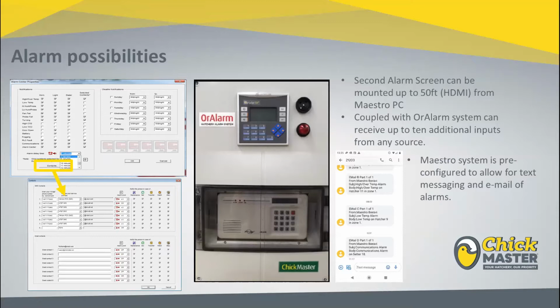The system also has the ability to disable notification by selecting the day of the week you would like to disable it, and from what time to what time. And again, remember, you'll be selecting the times that you do not want it to send out notifications or dial out messages. There's also an alarm delay built into this system, and the idea with the alarm delay is, one, give it some delay so you don't get every little nuisance alarm that triggers, but also don't give it a huge delay, maybe somewhere between 1 to 3 minutes, I would say.